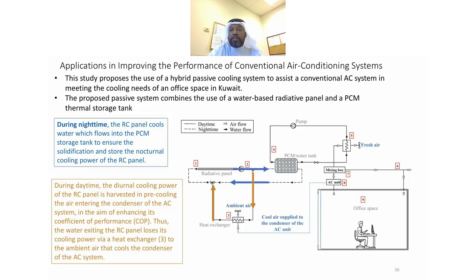At the same time during the day, the PCM that solidified overnight allows us to harvest the cooling saved in the PCM water tank via heat exchanger 5. This water flows through heat exchanger 5 and exchanges heat with the fresh air, which mixes with the return air supplying the air conditioning unit with reduced temperature fresh air. So we benefit from radiative cooling in two ways during the day: reducing the ambient air temperature going to the condenser, and reducing the temperature of the fresh air going to the air conditioning system.